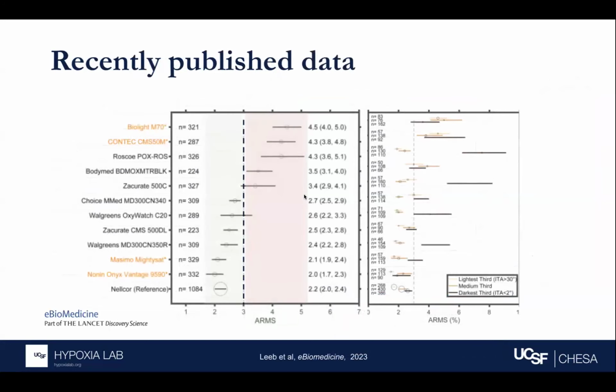We published some of these data about 6 months ago. One thing to note with this data set that I'm showing here that was published, these cohorts were smaller. These were not the full 40, 50 that we have today. This was from a year ago, so this was the small initial cohort of 10 to 15 max, 15% darkly pigmented. Here we showed that on the left-hand side of the dotted line, which is 3% ARMS, so like the FDA threshold, a good number of the devices were passing, but several devices did not, clearly here.